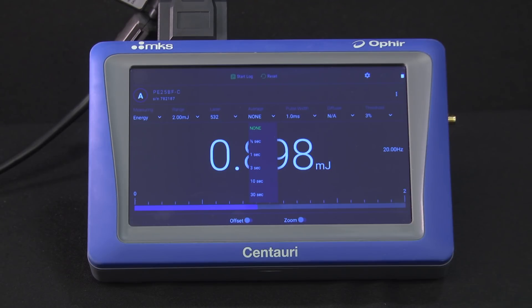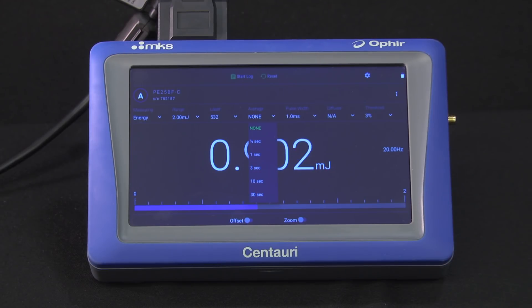Average displays a running average over a selected time, rather than the real-time instantaneous reading. This is useful when you need to measure an unstable beam. It's also accessible from the functions screen.